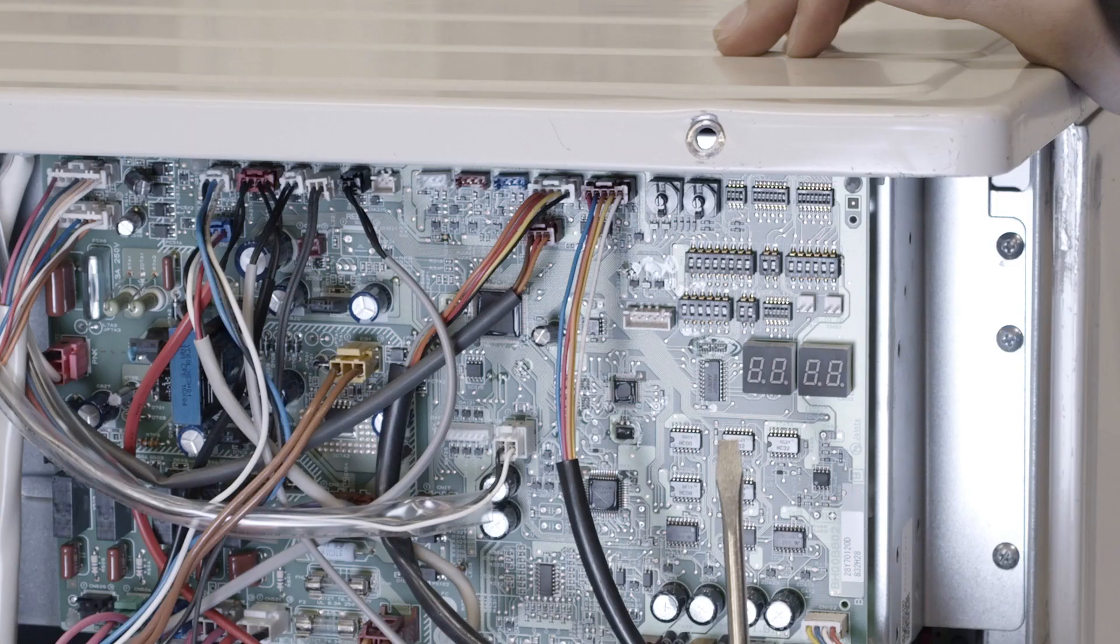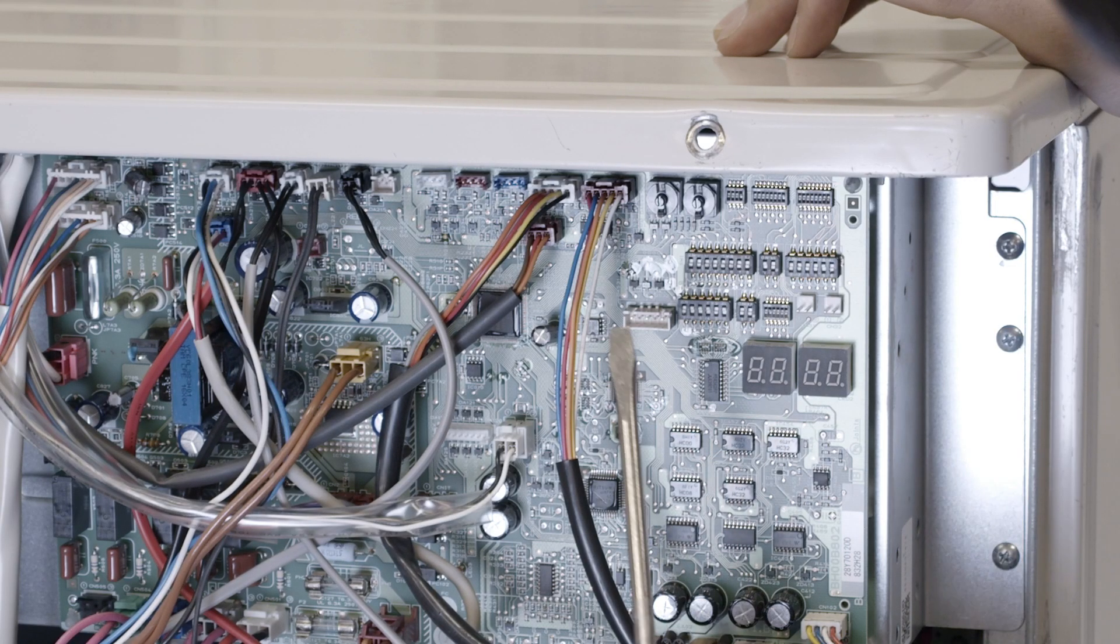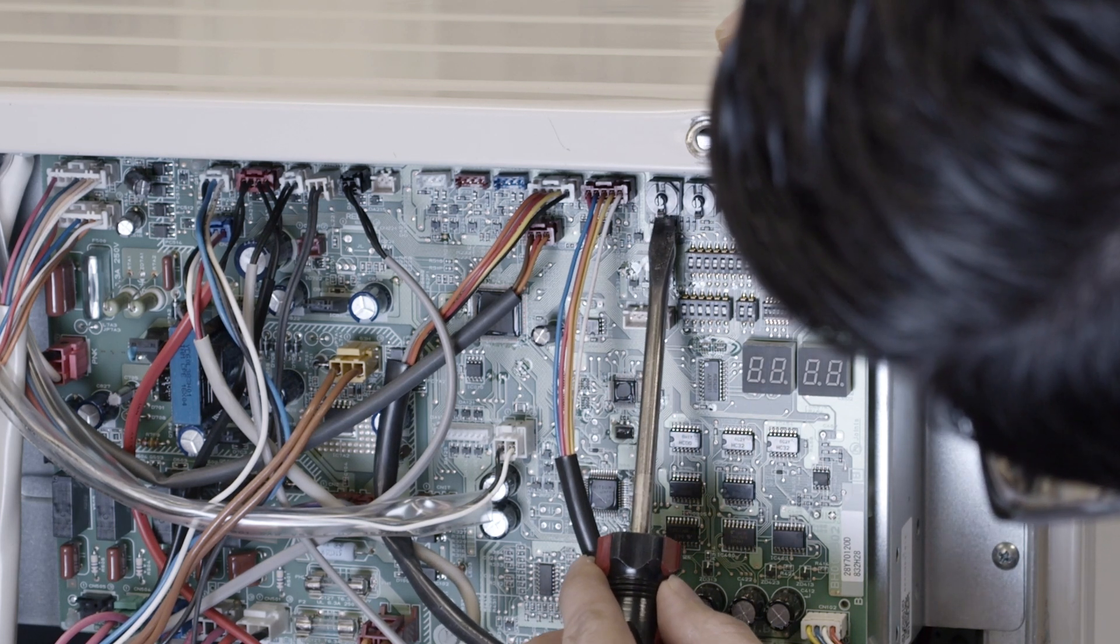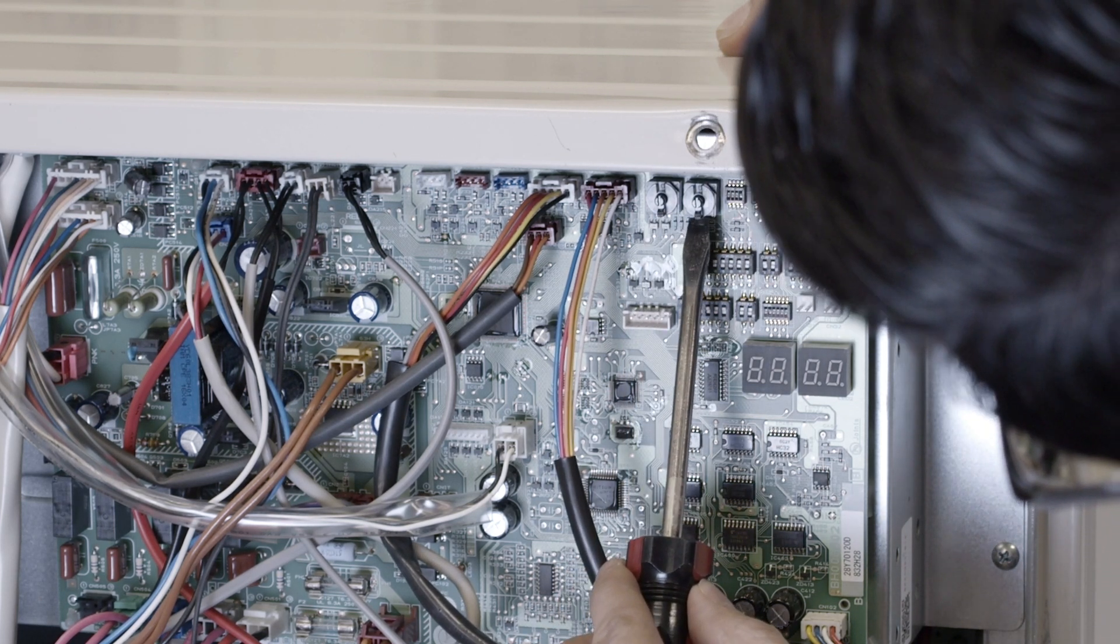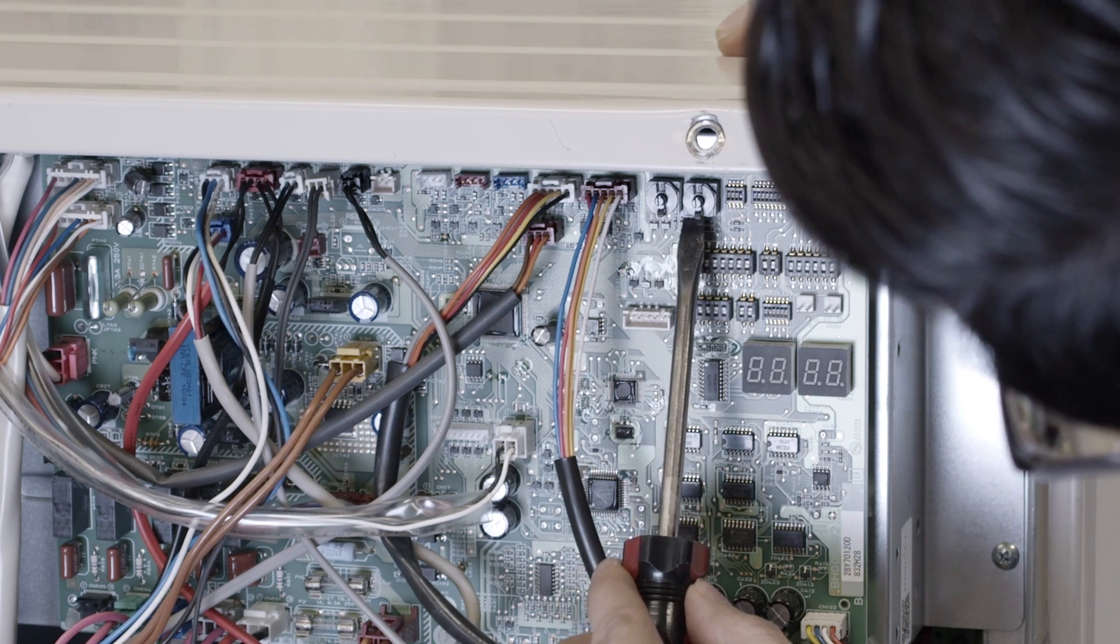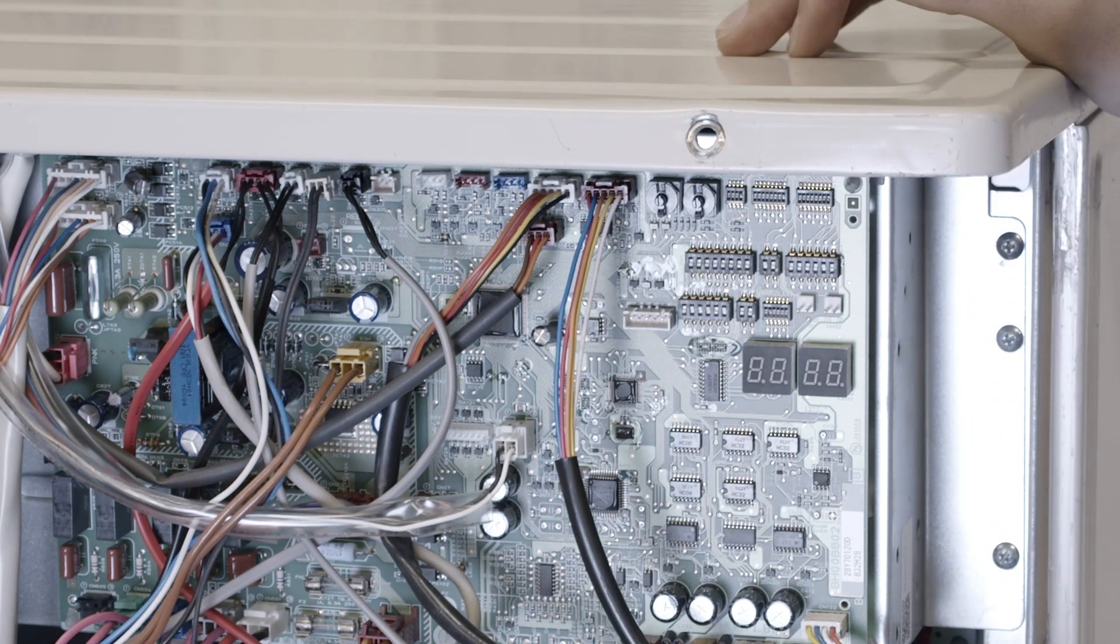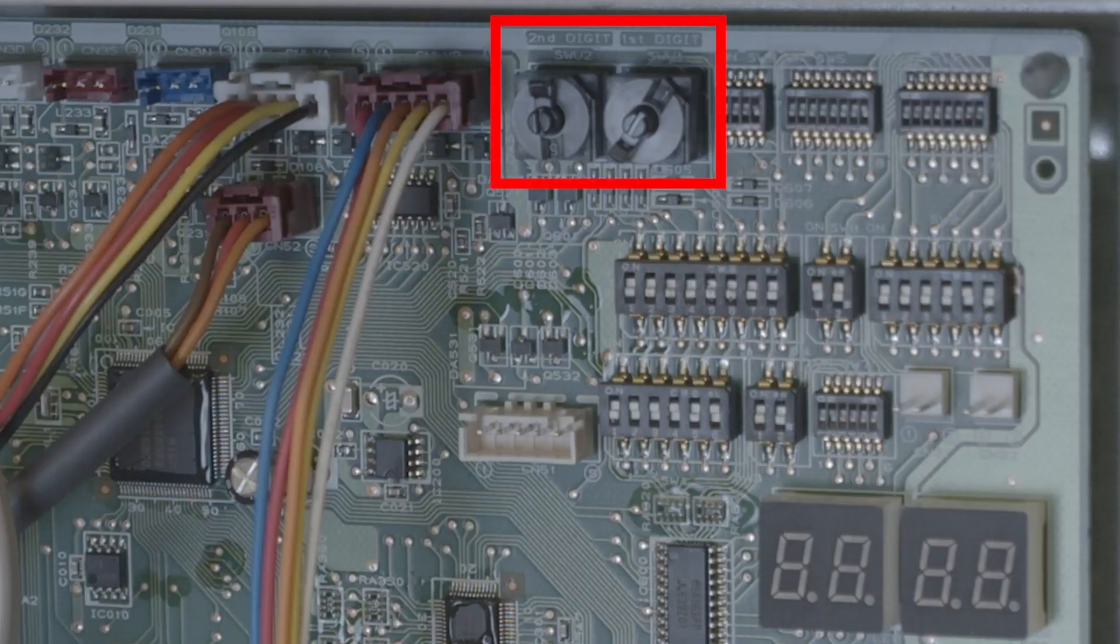In this video we address the branch box as 01, which means you'll address the outdoor unit as 51. To do that, you'll set your rotary dial SW2 to 5 and SW1 to 1.